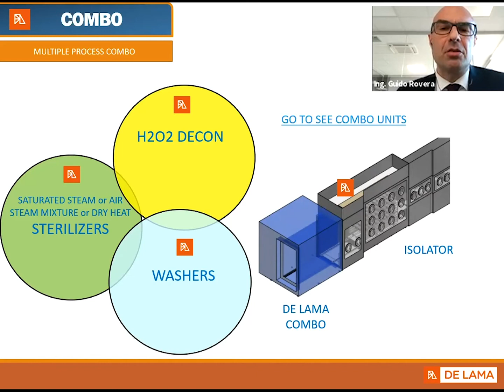Then whatever of these units can be integrated with whatever type of isolator using the technology of the magnetically driven sliding doors. So to summarize, we have a sterilizer that can be whatever type. We master also the hydrogen peroxide technique, either in decontamination or sterilization mode. And we master the technique of washing. These three techniques can be either combined together or in standalone mode, and they can be integrated into the isolator. The presentation refers obviously to a concept that is not a concept only, but several units have already been manufactured and sold all over the world with the same techniques.